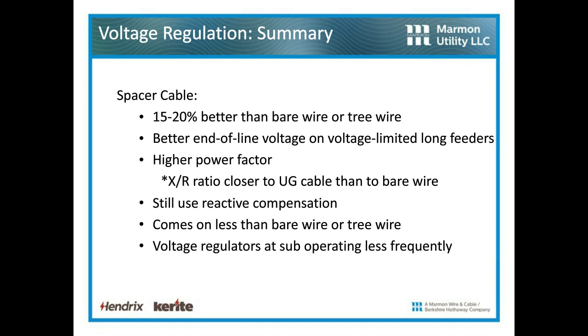It's going to have a better, 15 to 20% better end-of-line voltage on any feeder, but certainly on voltage-limited feeders. It's going to have a higher power factor. The X over R ratio of a spacer cable line is closer to underground cable than it is to bare wire. And we'll probably still use reactive compensation, switch cap banks, but they're going to come on a lot less than with bare wire or tree wire. And same thing, we'll still have voltage regulators at the sub, but they're going to be operating less frequently.